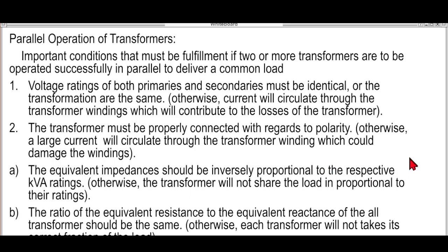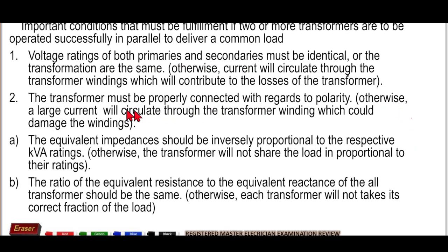Then to have parallel operation of a transformer, dapat meron siyang kaparehong voltage rating for both primaries and secondaries. Tapos yung transformer must be connected to its polarity, no? If you are going to have the impedances, no, yung total value ng ating winding sa ating transformer must be inversely proportional to the respective kVA ratings, no? So otherwise the transformers will not share the load. If the equivalent resistance and the reactance of all our transformers is not the same, then the transformer will not take its correct fraction of the load.